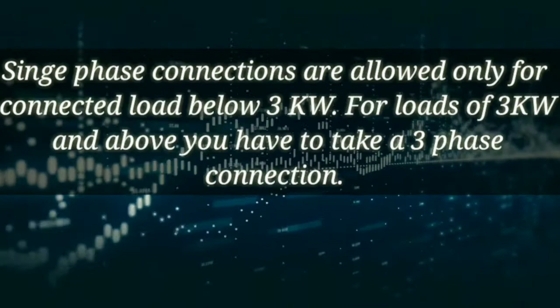Well, I will answer this part of the question. Single-phase connections are allowed only for connected loads below 3 kilowatt. For loads of 3 kilowatt and above, you will have to take a three-phase connection. Now, since all your domestic equipment and also industrial lighting equipment like the lights, fans, AC, fridge, etc. all work on a 230 volts single-phase AC supply, you will also need a neutral wire in addition to the three-phase wires so that all your loads are distributed between any one phase and the neutral. Now I'll come to the actual question.